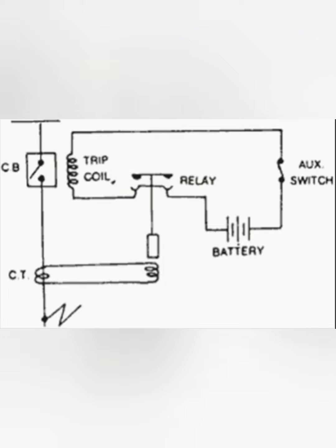So the circuit breaker is connected with your line and the current transformer which senses the line current. The relay is connected in parallel with your secondary side, which means the secondary value of your CT. Then for relay operation, battery connections are done, and the relay auxiliary goes to your tripping circuit.